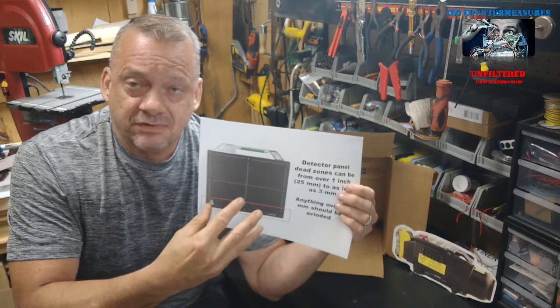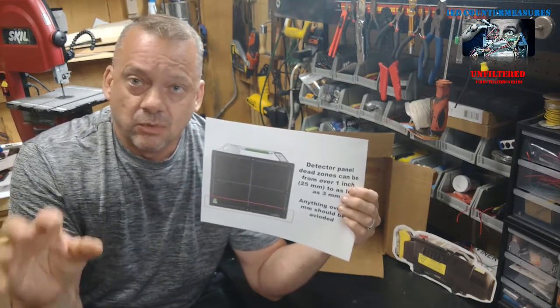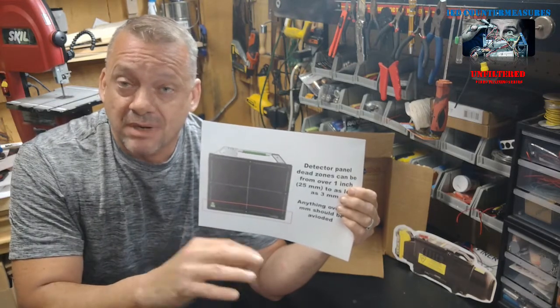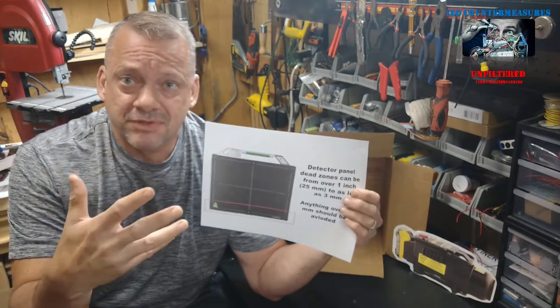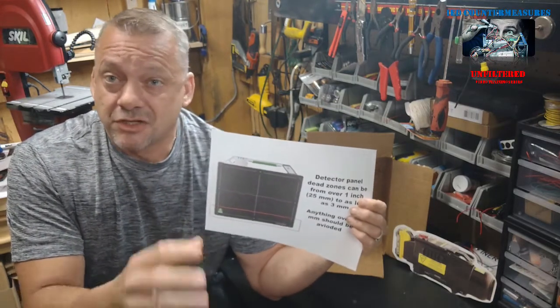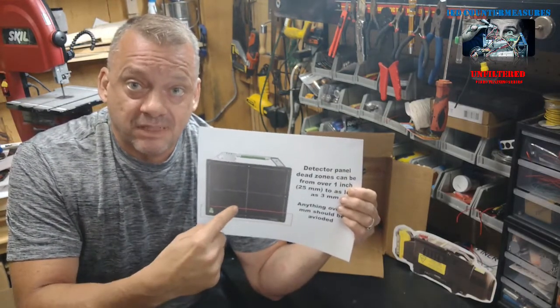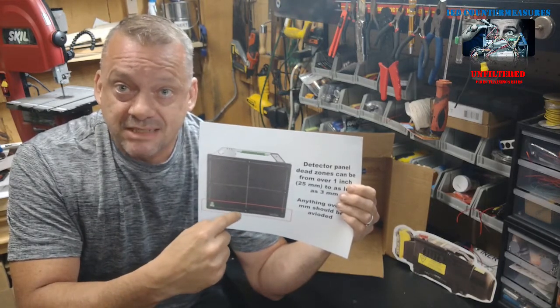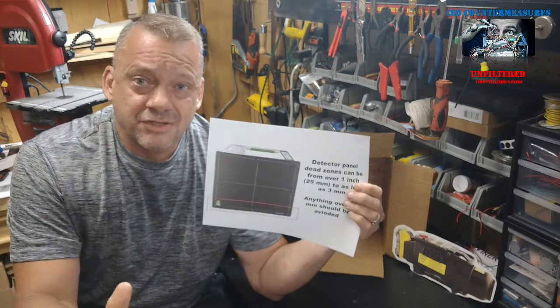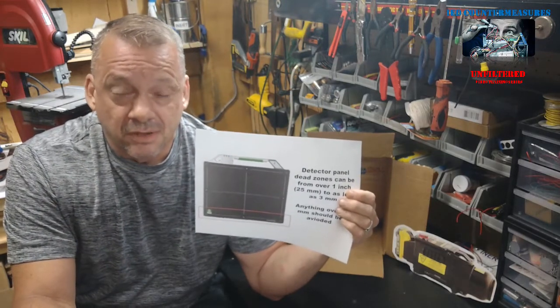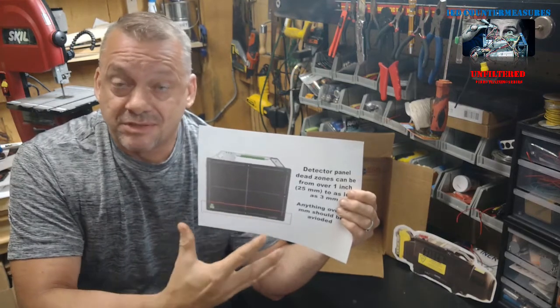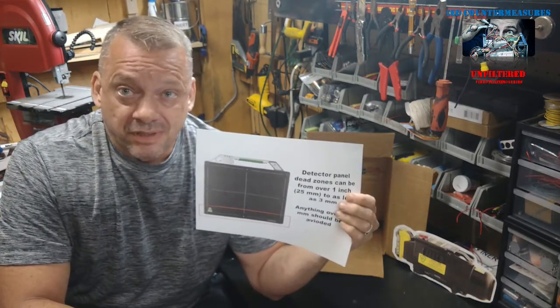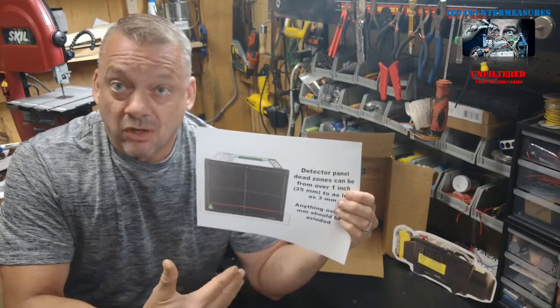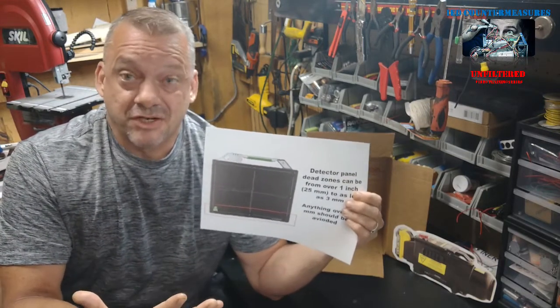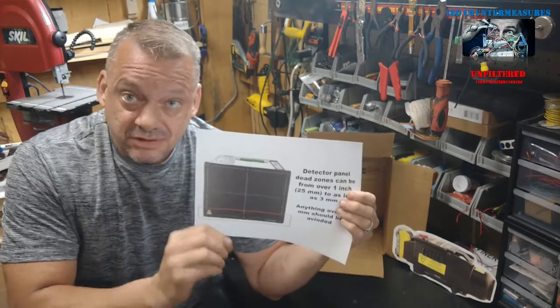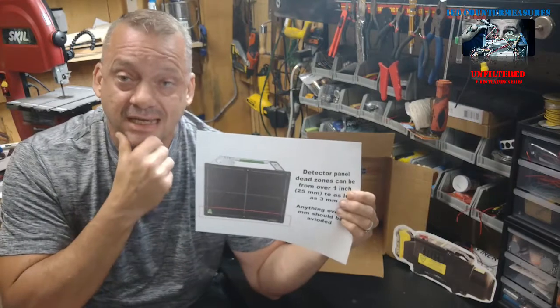Now, the first iteration of these panels that came out were straight up medical. We're now starting to see that the medical manufacturers these are bought from actually produce an NDT, non-destructive testing, or a security type panel. These panels will typically have a much lower bottom dead zone on the panel. The best you're going to see is around 3 millimeters. And from an engineering perspective, based on how these are designed, they really can't get any lower than that. Basically, from an engineering side, they can't get the scintillators and the detectors down any lower inside of the casing.